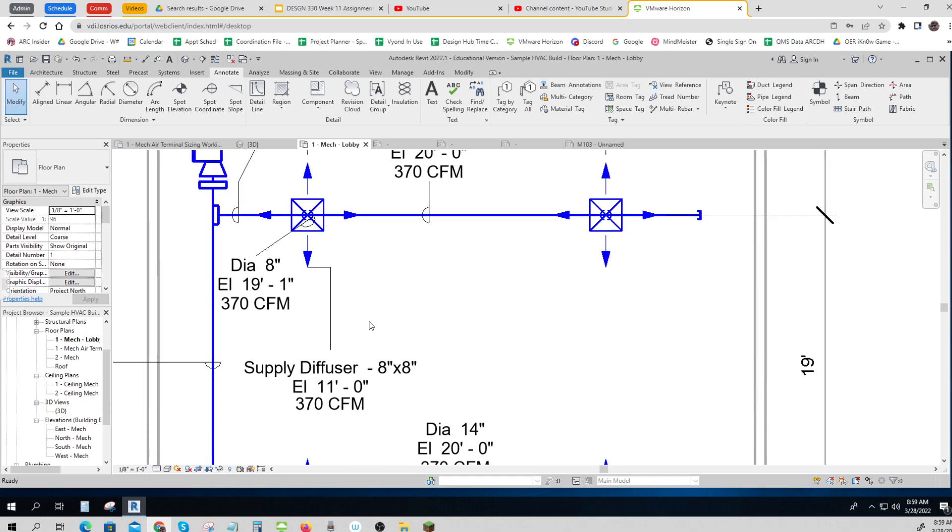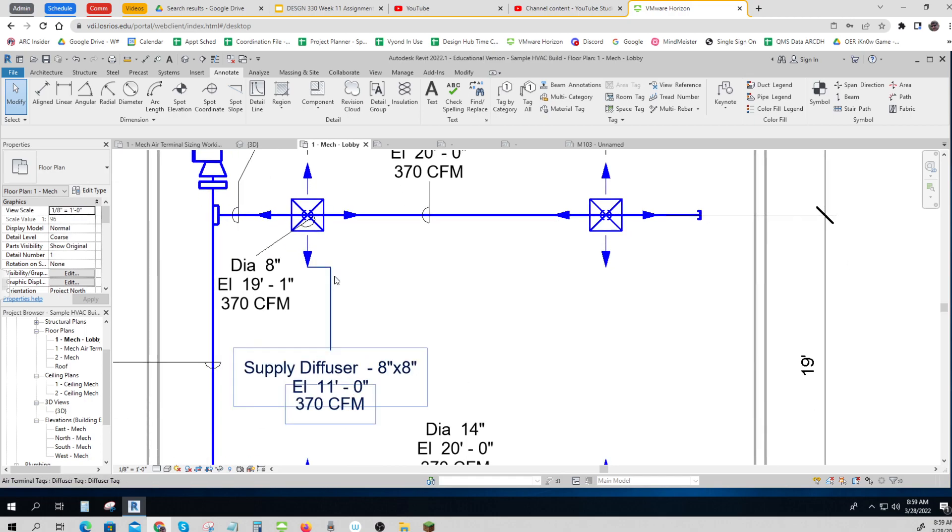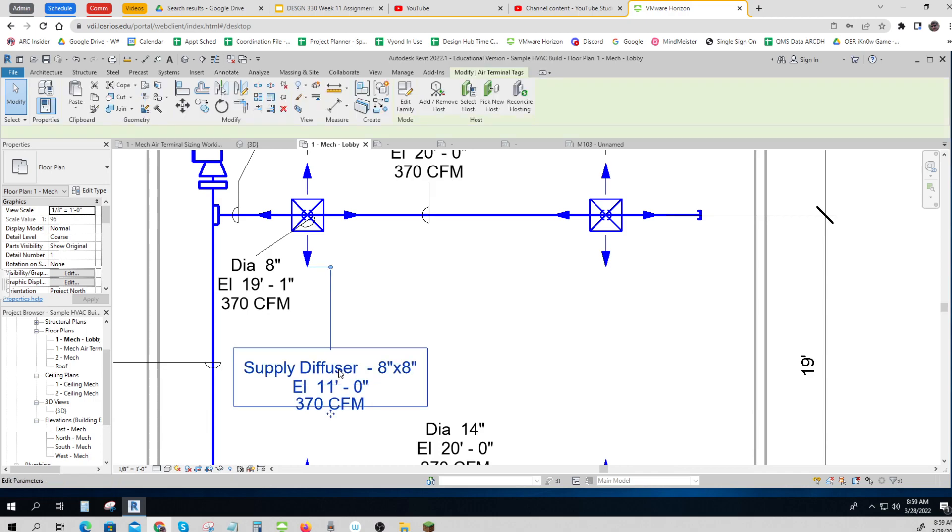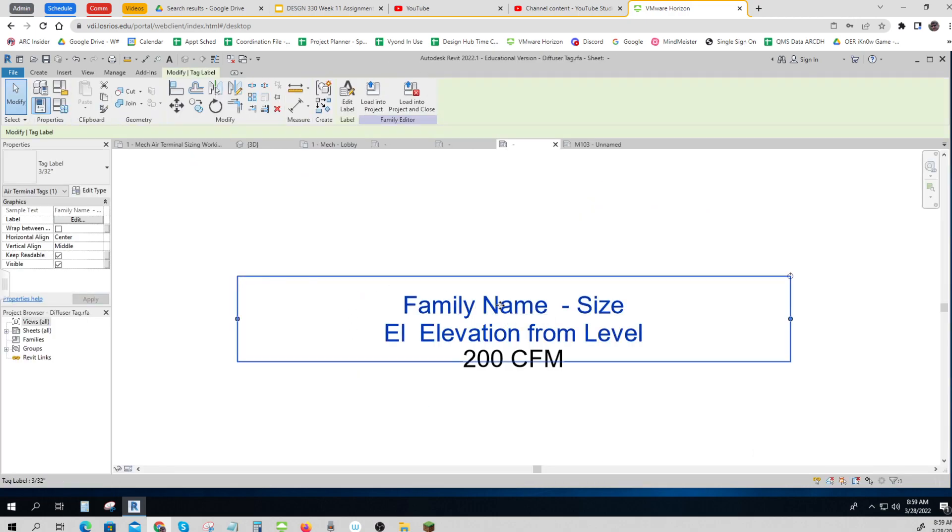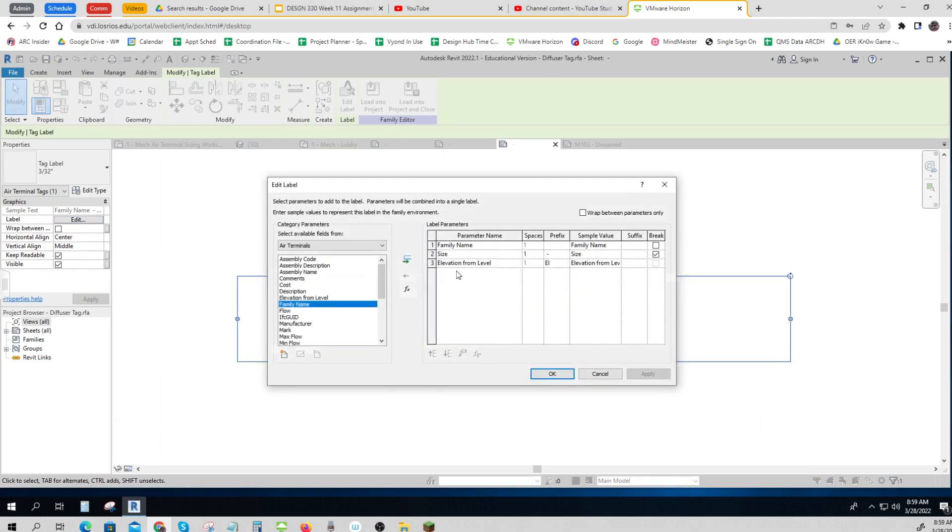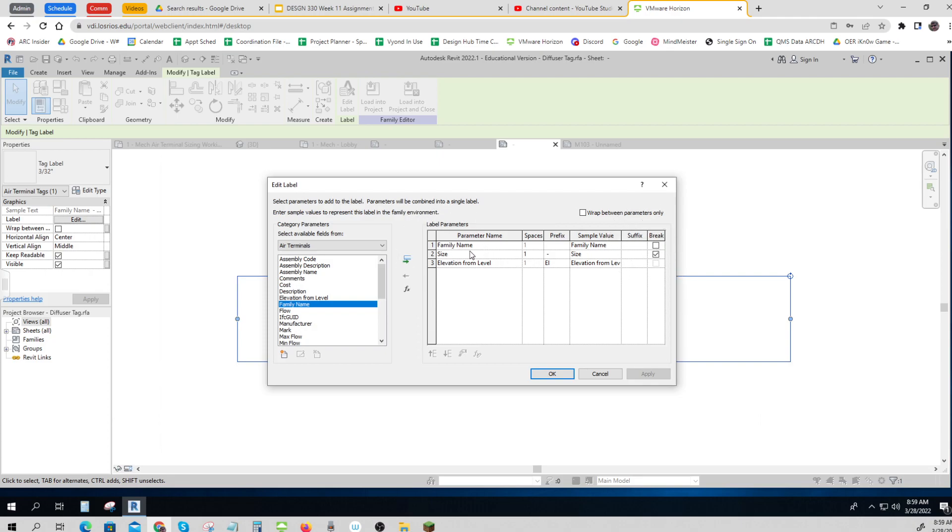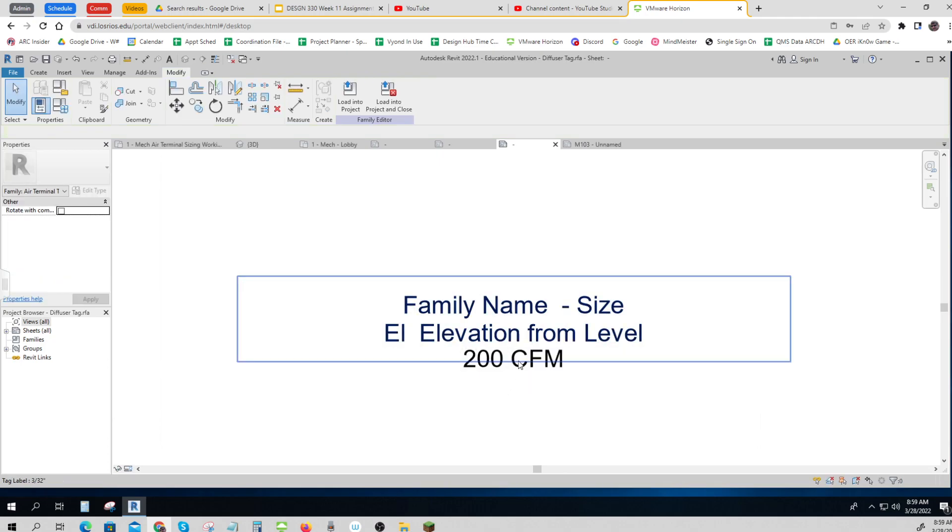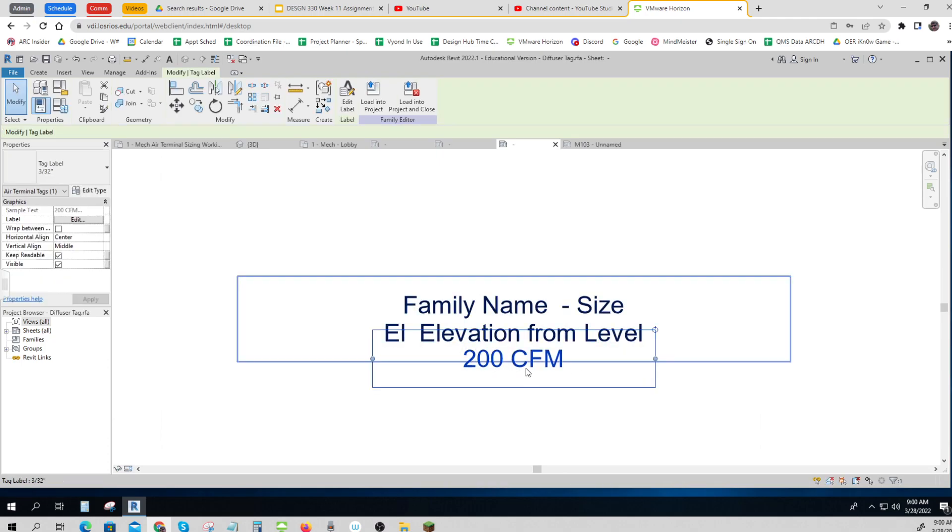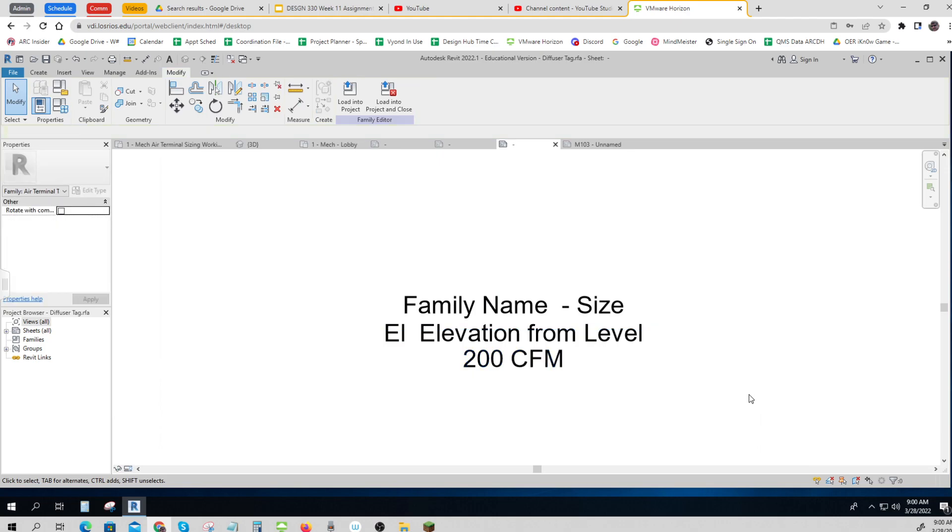And then let's take a look and see how I made my supply diffuser say all of this. So once you put it in there, you'll double click on it again, and click on it, and we'll see that I did a family name without a break, and then the size. And I put a dash in front of the size, and then I put a break. And then I put the elevation. So those were the three that were on that, and then this is a separate one and I just left it alone.